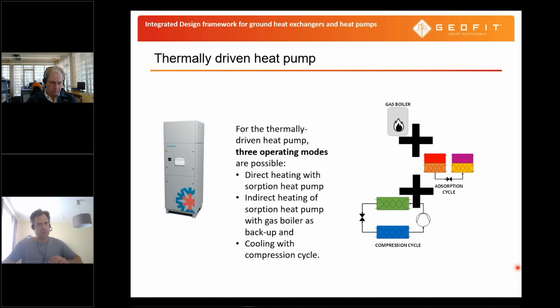Yeah? Because just generally speaking, those systems, thermally driven heat pumps, have an inherently lower COP. COP is the coefficient of performance, which gives the amount of heating compared to the input you need to provide. So that is, for, let's say, electrically driven heat pumps, in a range between 3 to 5. Yeah? And here, for a thermally driven heat pump, we have lower COPs than for electrically driven heat pumps, which in turn also means that we have a low amount of heat at the evaporator.